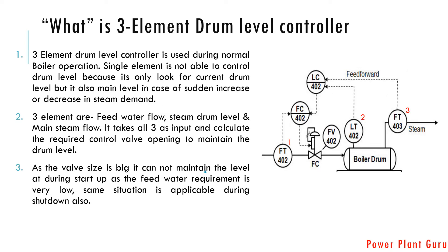The three-element level control looks after all inputs, outputs, and the current drum level — specifically, the rate of feed water coming in, the rate of steam going out from the boiler, the current drum level, and also the rate of change in those parameters. Based on those rates of change, it calculates and gives a set point to the feed water controller.